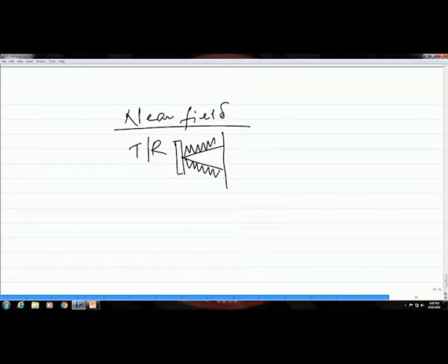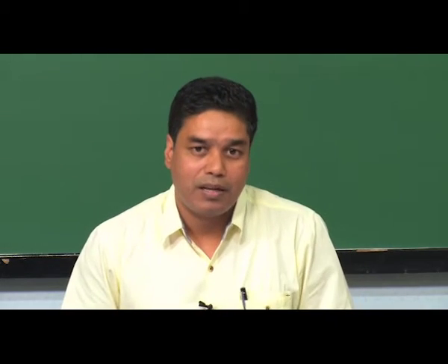Okay. So, in this case in the near field, if it is still vibrating, that means it is still transmitting. So, if any echo comes back within that time when it is still vibrating, then it will not be able to receive that echo. Okay. And that can happen if that echo comes back very fast.